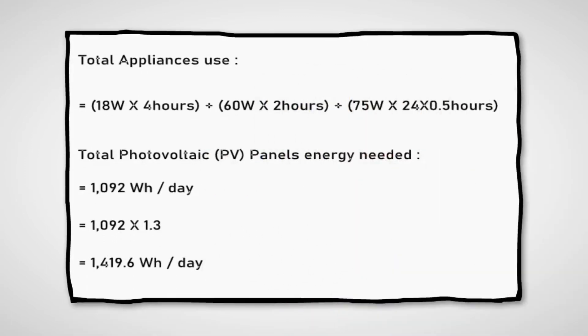To determine the power consumption demands, you will be able to estimate the amount of energy to be supplied by the solar PV system. Calculate the total watt-hours per day for each appliance used, and then calculate the total watt-hours per day needed from the PV modules. After determining the total watt-hours per day, multiply it by 1.3 for energy lost in the system.